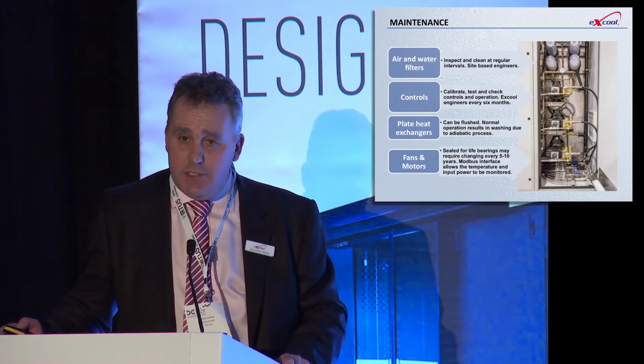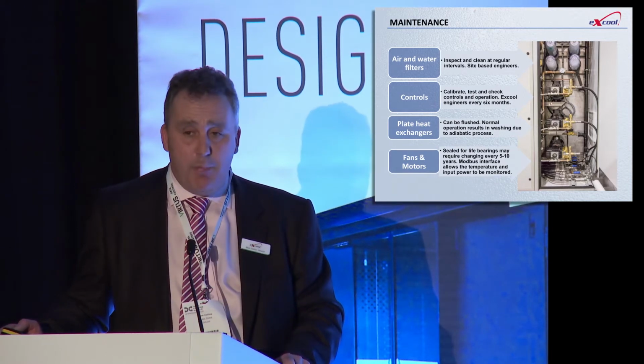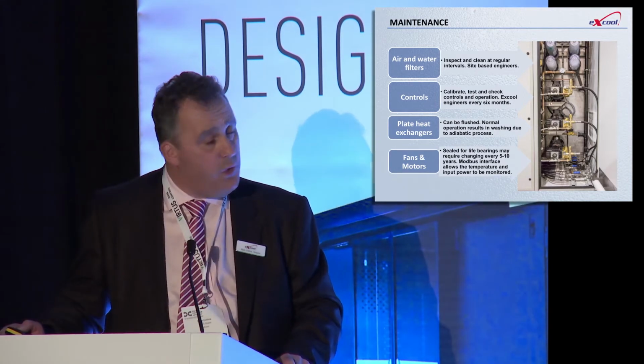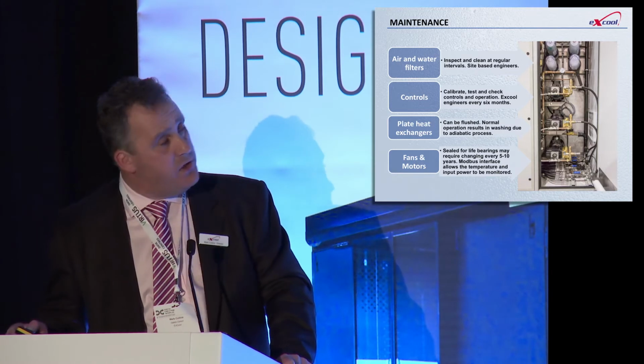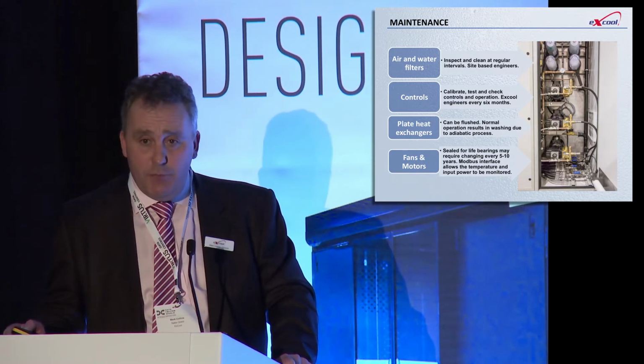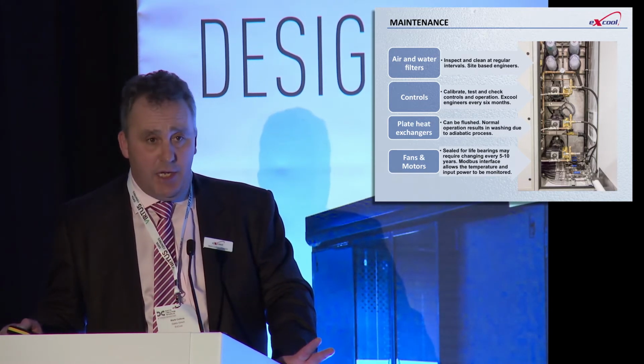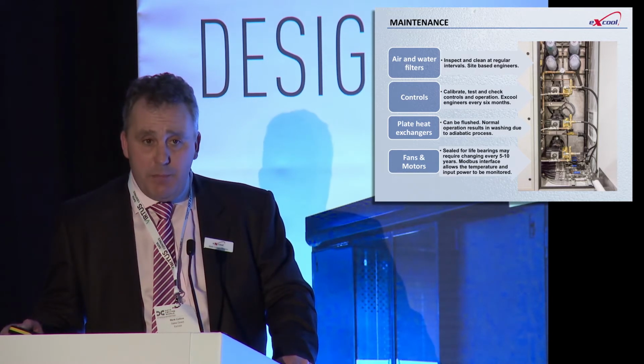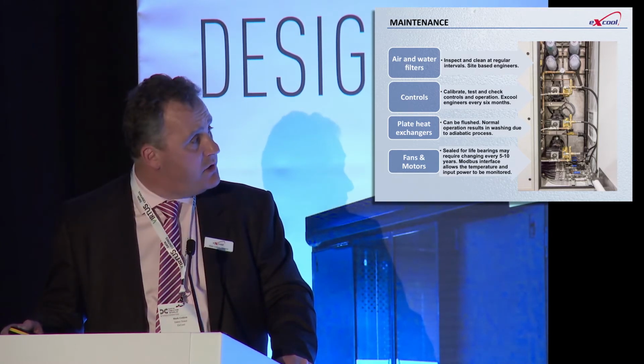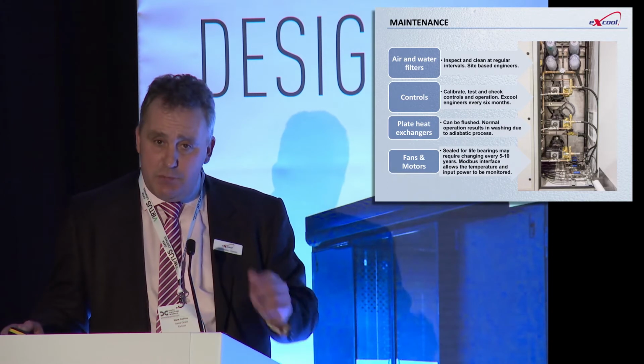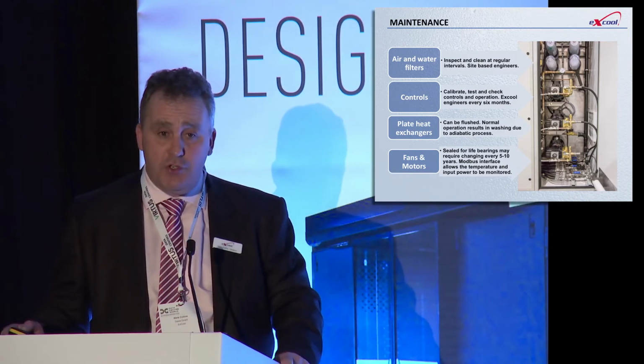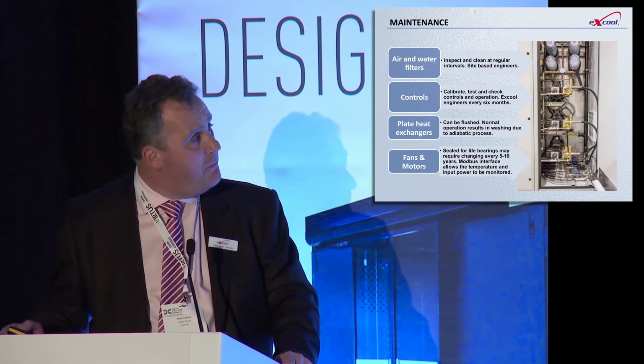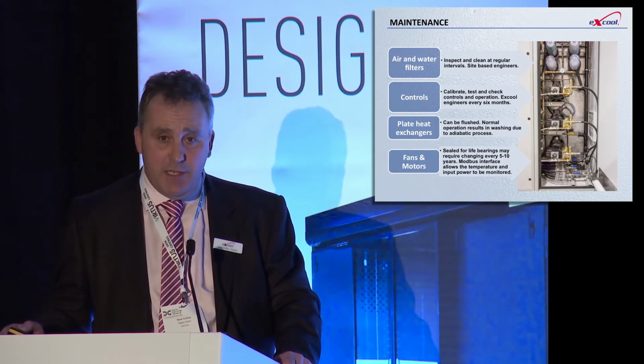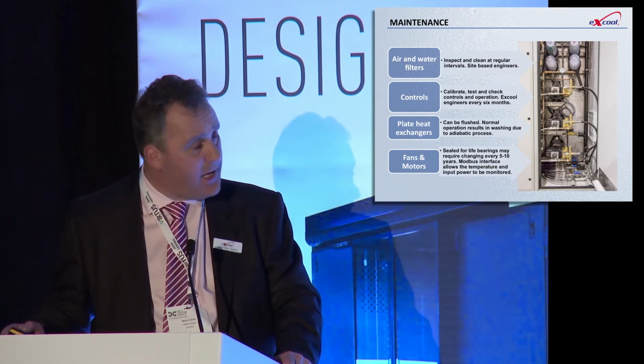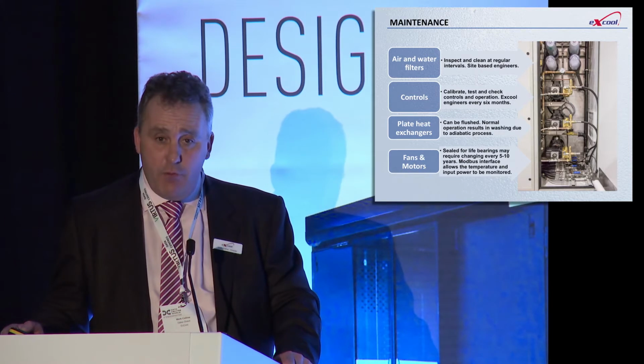So in terms of maintenance, I touched on this earlier on. We have a basic maintenance regime, which is to inspect and clean water filters and air filters at regular intervals, and that can be done by site-based engineers. Controls, we will come to site and calibrate and test those once or twice a year. The plate heat exchangers themselves are self-cleaning because we're spraying water on them regularly in the summer, but they can be flushed if they do get contaminated. We can't imagine how they would, but they can be pressure washed because they're made of a very robust material.